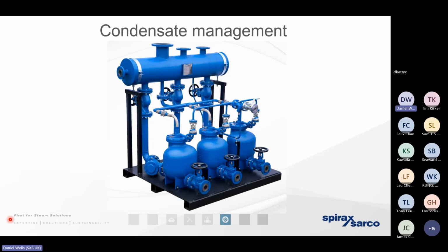It means the steam's going to be wetter with less energy present within it. So we're going to have an increased inefficiency, and we're also going to have a higher burden of maintenance. But I really want to focus on what's happening on the wet side downstream of the steam trap in this presentation.